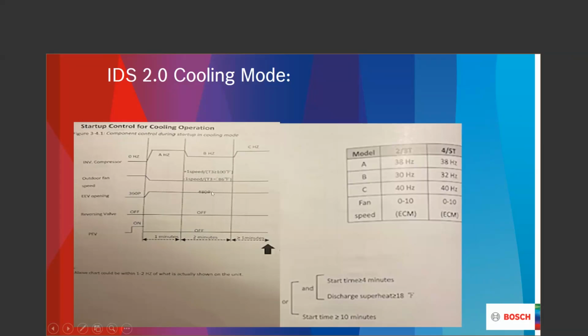Then we're going to go, you know what? We went through the 1 minute, we went through the 2 minutes, and now we're into the third stage. And the third stage is going to be the C hertz rating. And here we are in the 40s. So 2 and 3 ton, 4 and 5 ton, we are now at the 40 hertz rating. Staging is done every time the system comes on the 2.0 in the cooling mode.